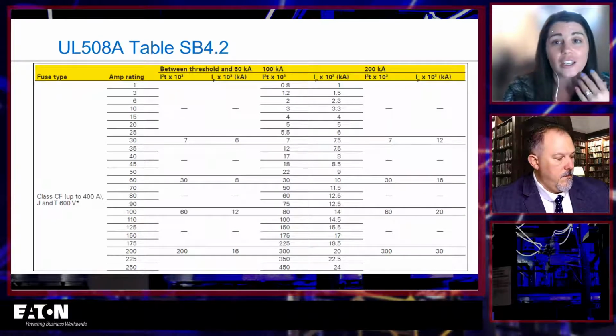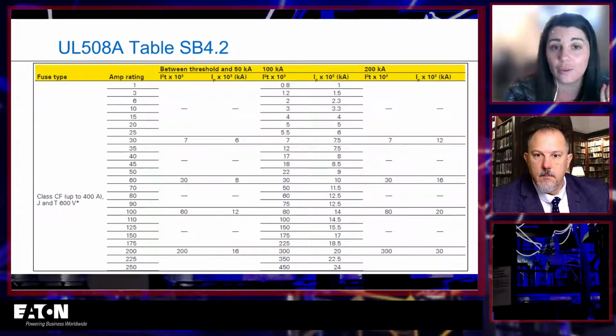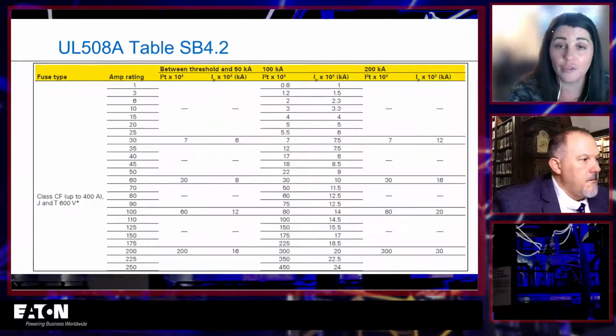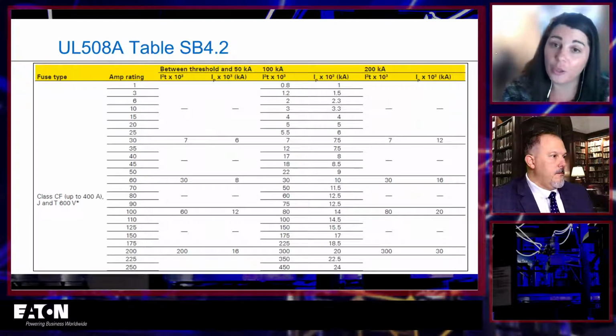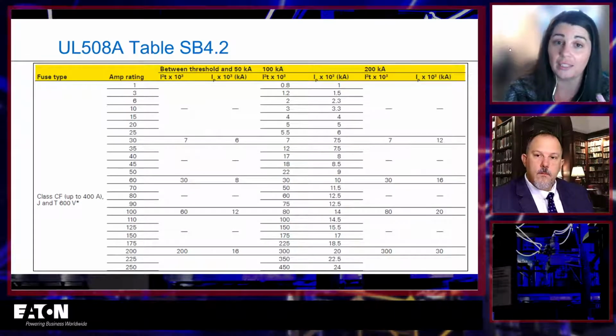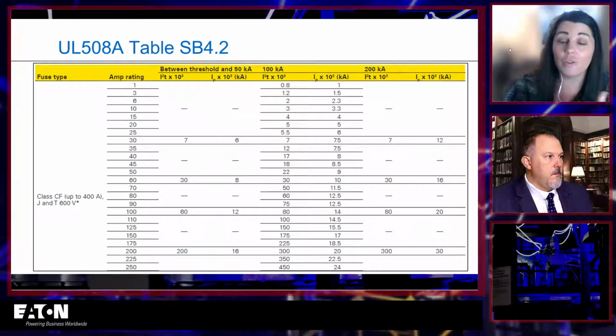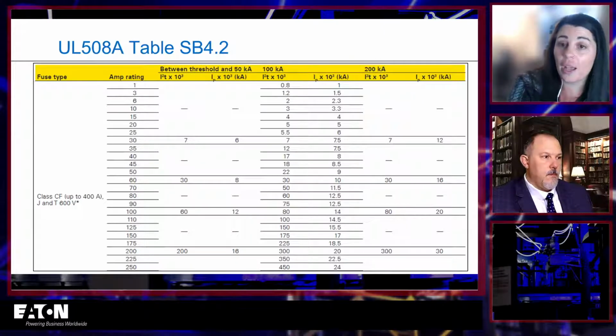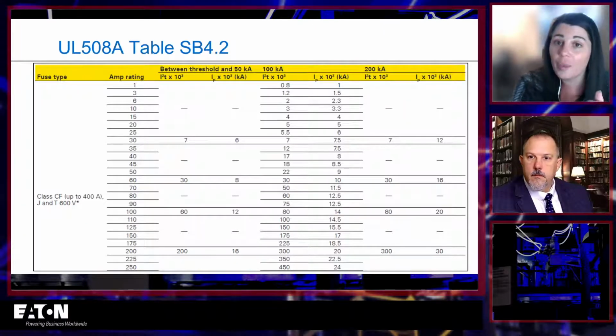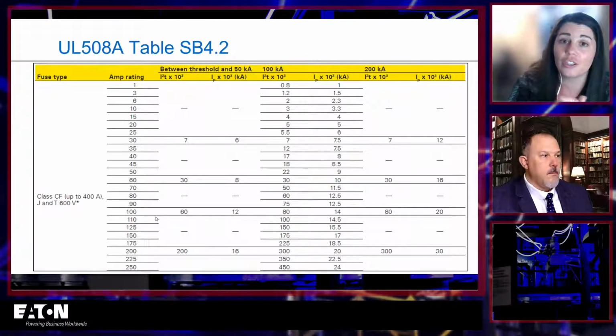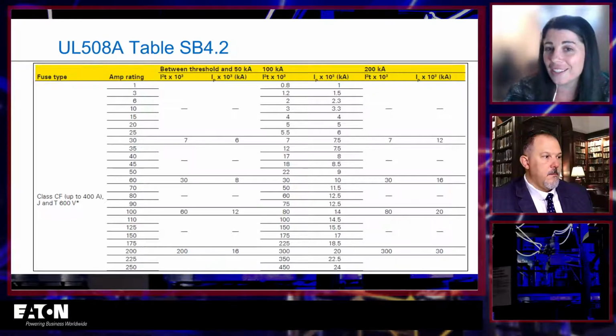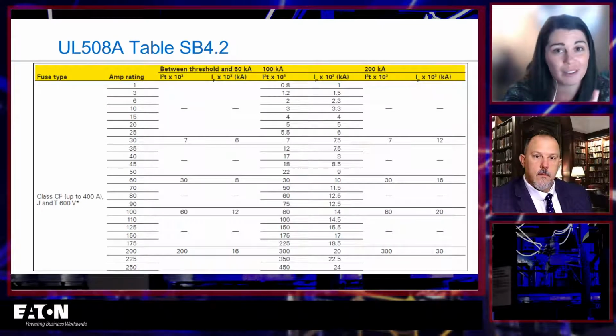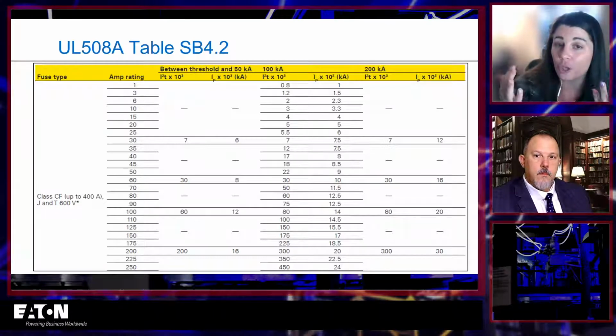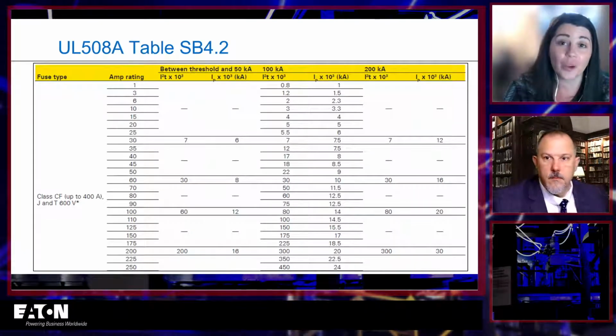And the logic for why they do that is because you might design a panel and install a specific manufacturer's fuse, and the first time that opens and someone goes to replace it, they're not necessarily going to replace it with the exact same fuse. So you have to design it for any fuse of that class as opposed to the specific one that you are using. So in a way it's nice, in that when you're designing your panel, you don't have to go look up every specific fuse. You just get to refer to one table, but this table might not give you as good of values as if you were able to use the specific fuse, because these are the maximum threshold limits for those fuses instead. So just an important thing to note about what we're using.